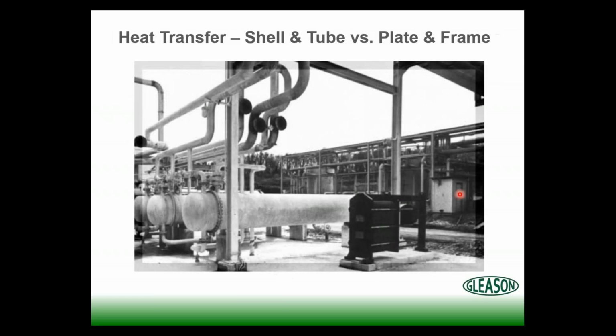So here's a good example of comparing the shell and tube versus a plate and frame. Both of these heat exchangers, this plate and frame and this shell and tube, do the same duty. And you can see the advantages there. Look at all the space this one takes up, and especially in a university setting, that can be a big deal. Not to mention, if you have to service this, when we pull this head off the bundle, we've got to have plenty of room to be able to pull that bundle out to service it. We can also change the number of plates. So if our process changes, we can add plates, take plates away, and it's also serviceable within its own footprint. So that's another big advantage there.